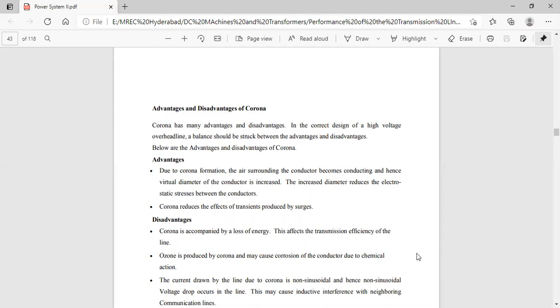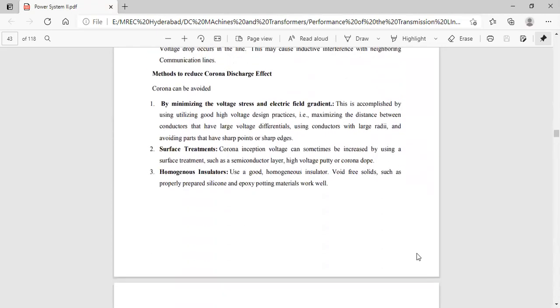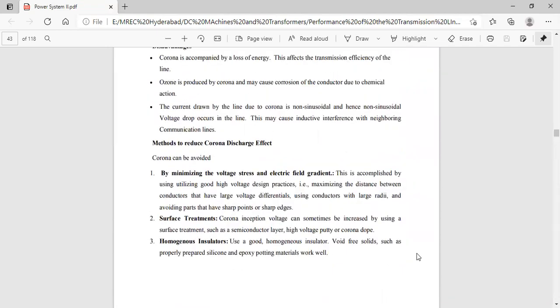Next are the disadvantages. The first one is that corona is accompanied by a loss of energy. This affects the transmission efficiency of the line. Ozone is produced by corona and may cause corrosion of the conductor due to chemical actions. The third point, the current drawn by the line due to corona is non-sinusoidal, and hence a non-sinusoidal voltage drop occurs in the line. This may cause inductive interference with neighboring communication lines. So these are the advantages and disadvantages of corona.